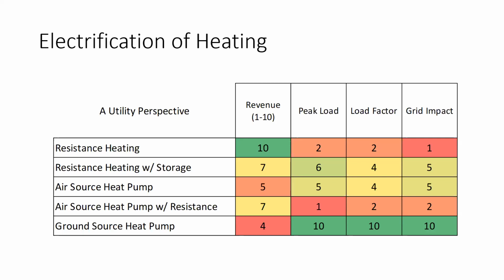One thing, just to put a fine point on that: if you own a home with an air conditioner and a gas furnace, your utility probably hates you, because you're using maybe 6 kilowatts all summer. Then on October 1st you start using your furnace, which only uses about 600 watts. So you cut your heating and cooling power usage by a factor of 10, and you just sit on that for 6 months until it gets hot again, or in San Antonio maybe just a few months. But the point is that utility company has to maintain that 6 kilowatts of infrastructure while you're burning gas all winter. That's expensive.